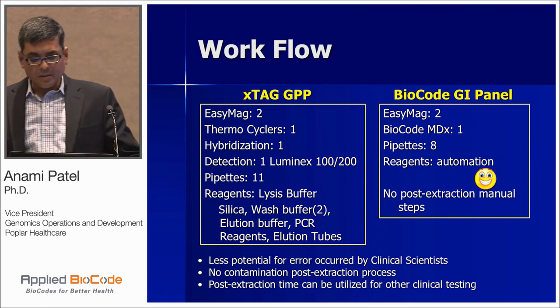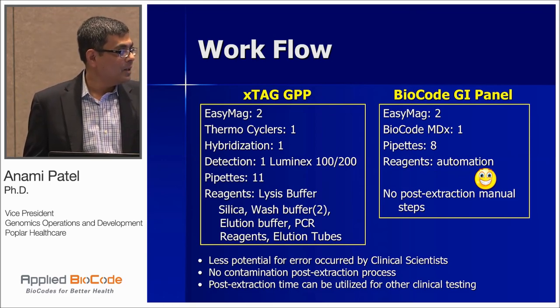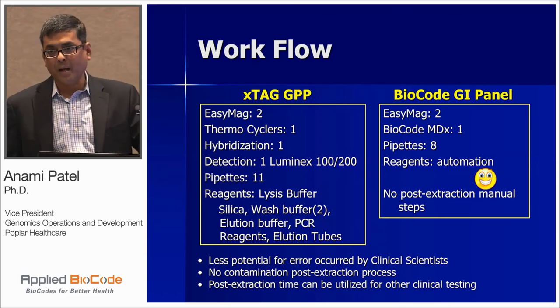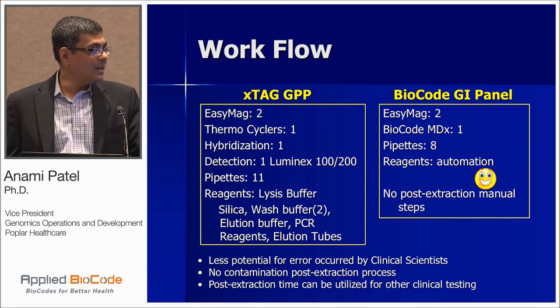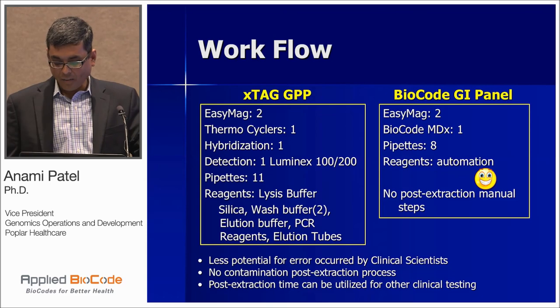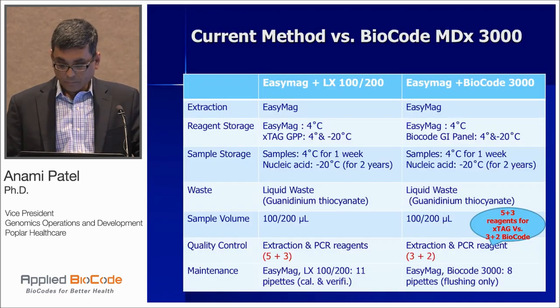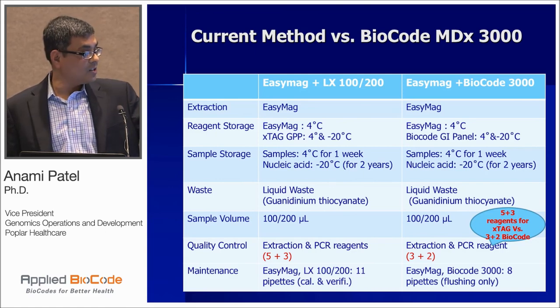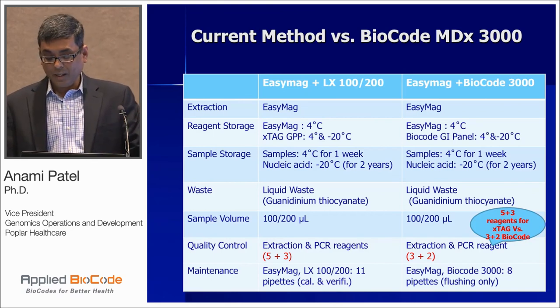Looking at workflow and maintenance requirements side-by-side: EasyMag and thermocyclers are the same. The difference I see is in the number of pipettes — with the current Luminex flow we require about 11 pipettes versus only 8 with BioCode, reducing pipette calibration and maintenance costs. With no post-extraction manual steps, lab technologists love the semi-automation, as it means less potential for error and contamination by clinical scientists. From a quality control perspective, BioCode requires 5 reagents to track versus about 8 reagents with the current workflow.